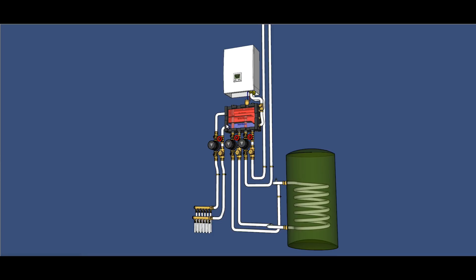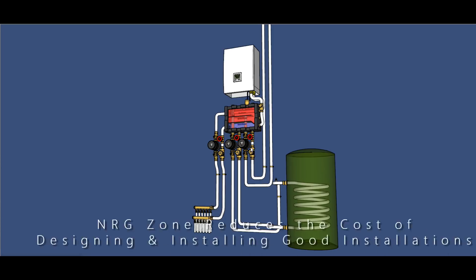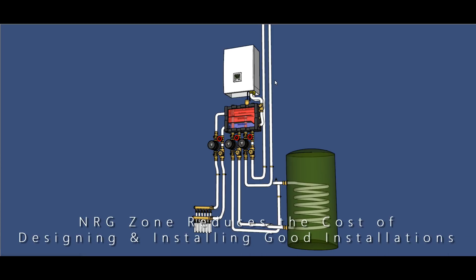If you had a circuit upstairs, you simply drop down below the unit. Drop as far as possible - I like to drop maybe 300-400mm or 12 to 15 or 20 inches below the manifold. Pump down around and back up to your circuit upstairs. The non-return valve fitted on the return will catch any inadvertent heat drift that would otherwise heat the radiators upstairs.